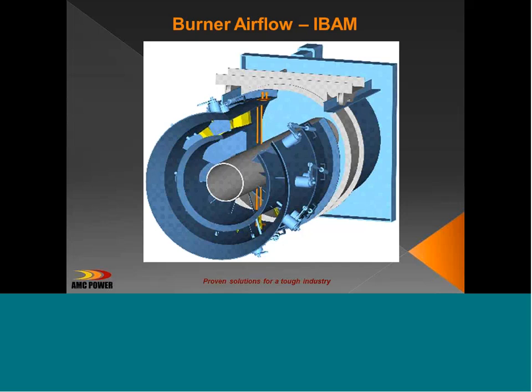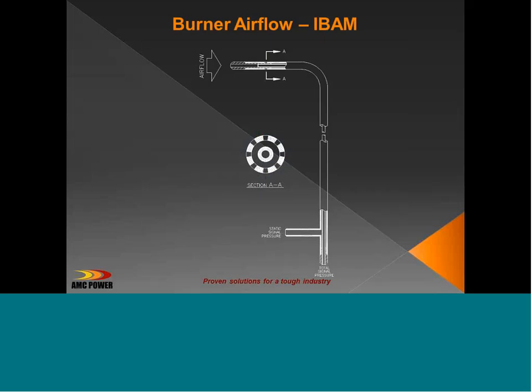This is burner airflow measurement that I want to talk about now. This is a depiction of a generic low NOx burner, and in orange are our pitot tubes that are used to measure airflow. I'll talk very briefly about airflow measurement in general. I'm sure you all are aware how pitot tubes work. You measure a differential pressure, and you can convert that into air velocity, which can be converted into flow. This is a standard pitot tube.